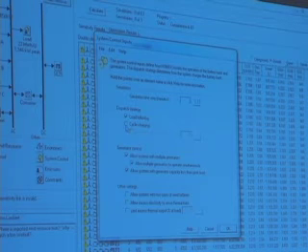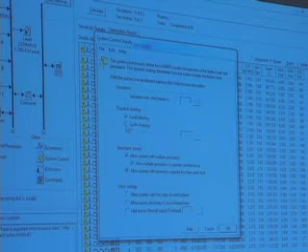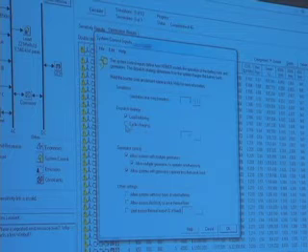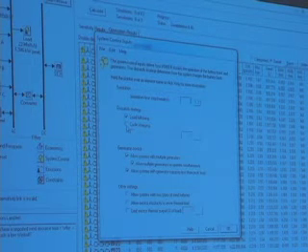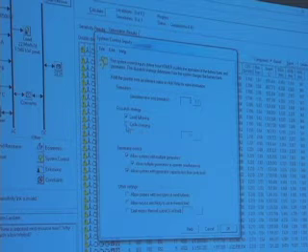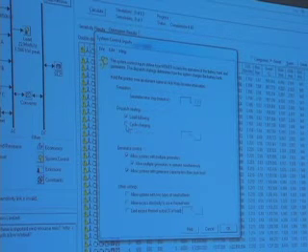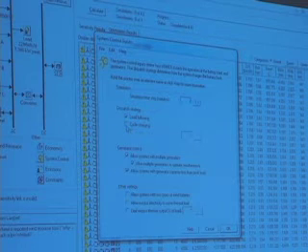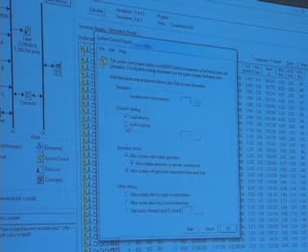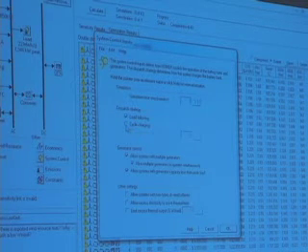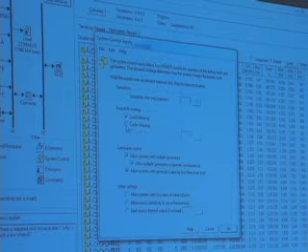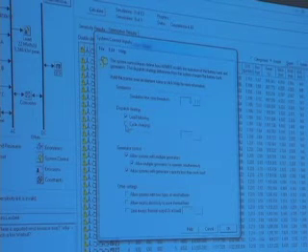So even though some operators may run a large generator when a smaller generator could meet the load, what Homer does is it says, of all the different options I have for meeting the load, what's the least cost option? So Homer's an optimization model. Some of your operators may not be optimizers. So in that sense, Homer's going to sort of overperform what will really happen in the field.